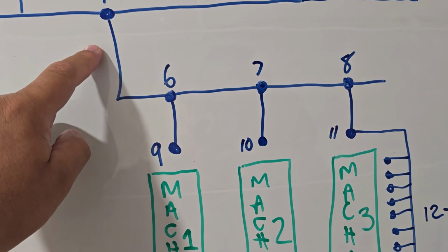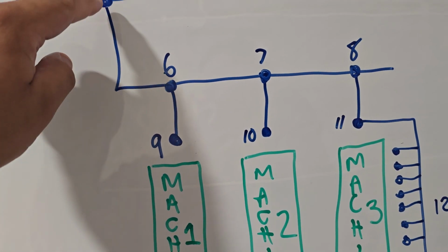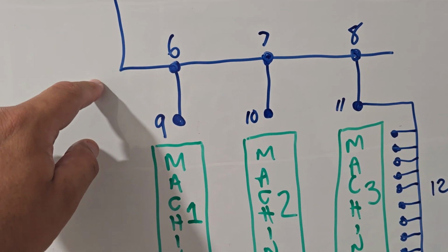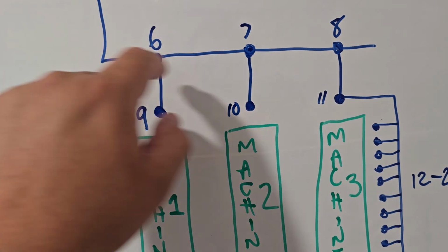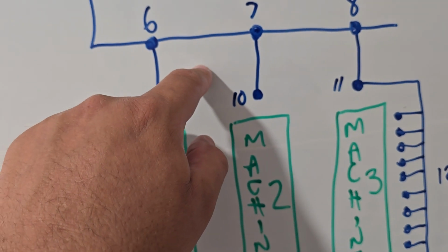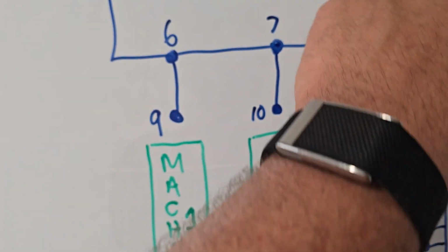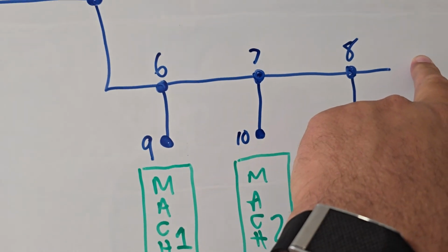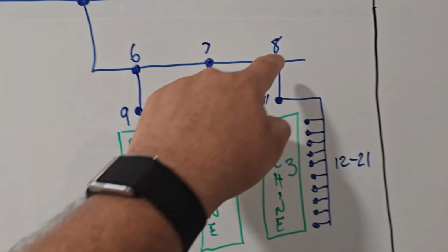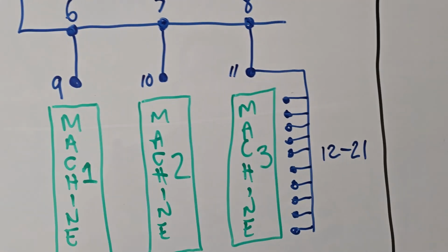So we need to be taking flow and pressure here, and we need to see at the best interval possible, we need to be able to see what's going on in this line against these other machines. That will be able to tell us if this line is sized correctly and or if there's a benefit to tying in this. But if we notice that there's also a problem here, this is where it gets really fun.